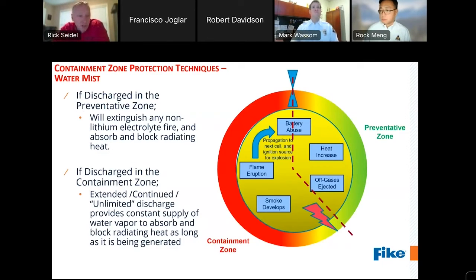Water mist, if discharged in a preventative zone, same thing, will extinguish any non-lithium electrolyte fire and work to absorb and block the radiating heat. And if it's discharged in the containment zone, you can achieve an extended, continued, potentially unlimited discharge to provide a constant supply of water vapor to absorb and block the radiating heat as long as it is being generated. So very effective for long-term continuous protection.